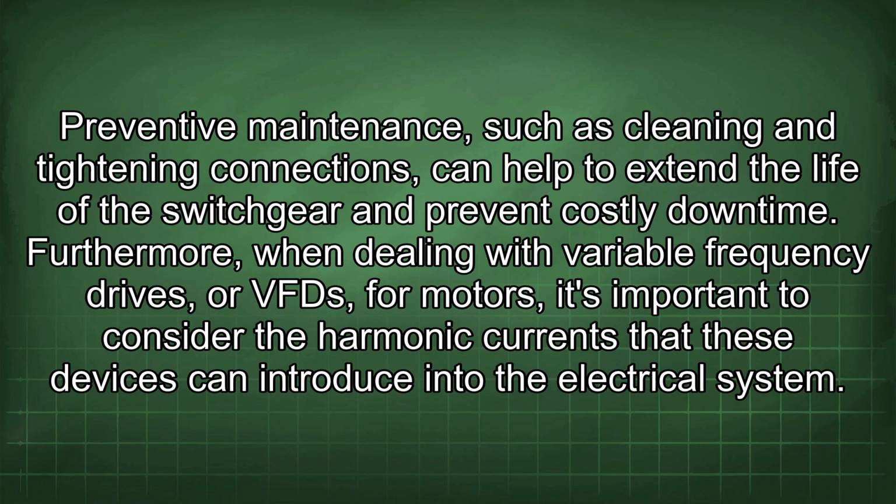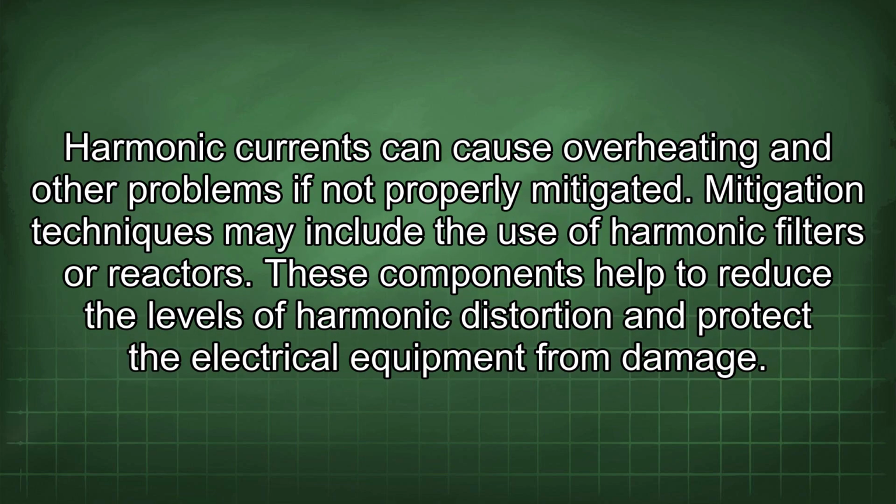downtime. Furthermore, when dealing with variable frequency drives, or VFDs, for motors, it's important to consider the harmonic currents that these devices can introduce into the electrical system. Harmonic currents can cause overheating and other problems if not properly mitigated. Mitigation techniques may include the use of harmonic filters or reactors.